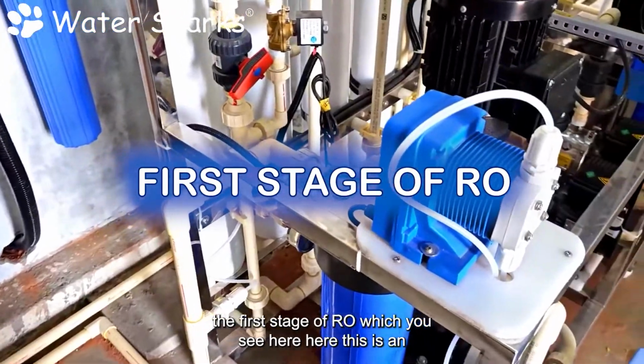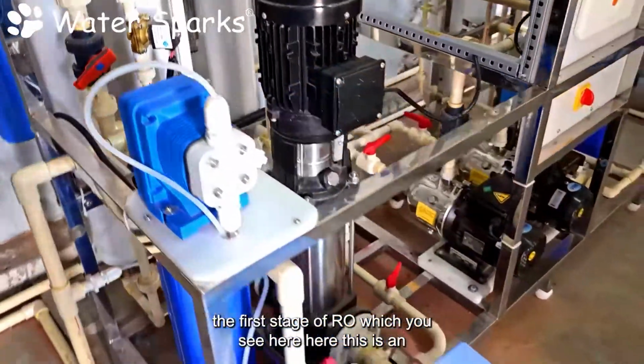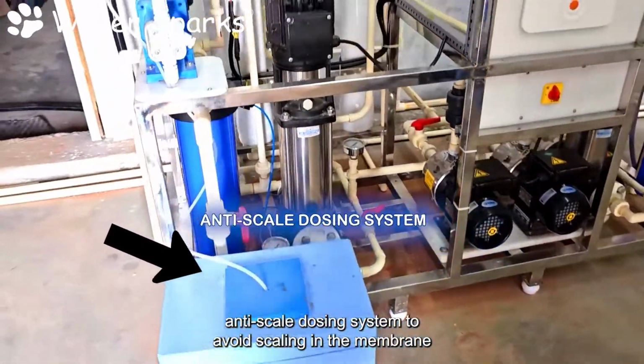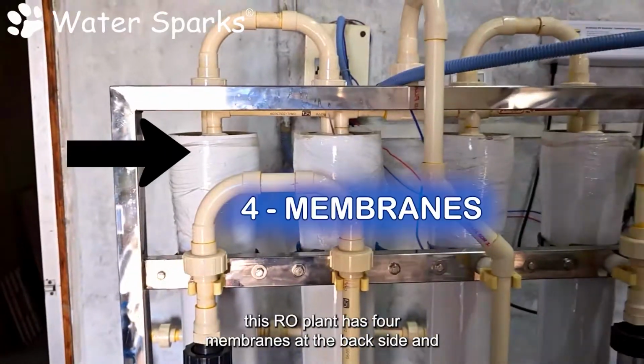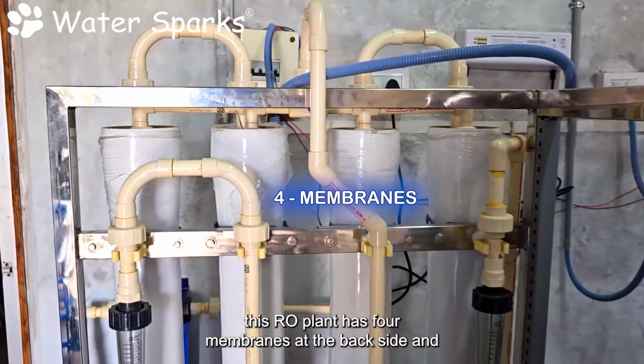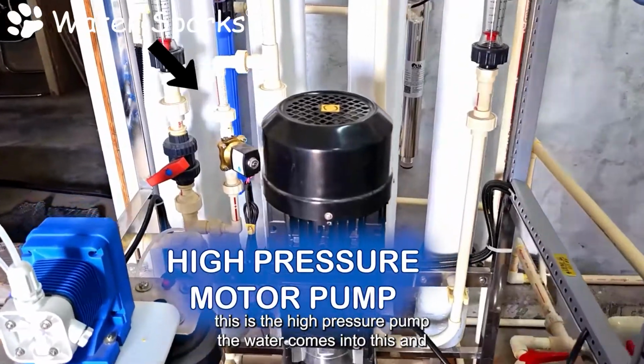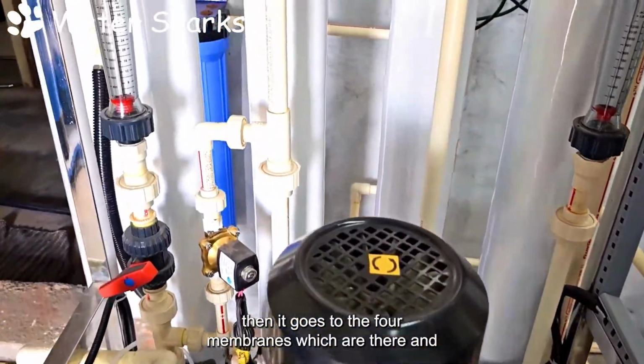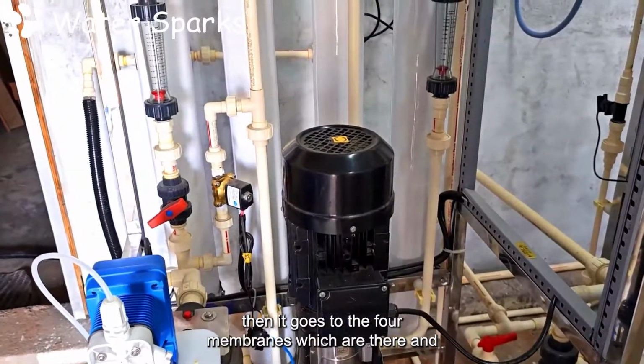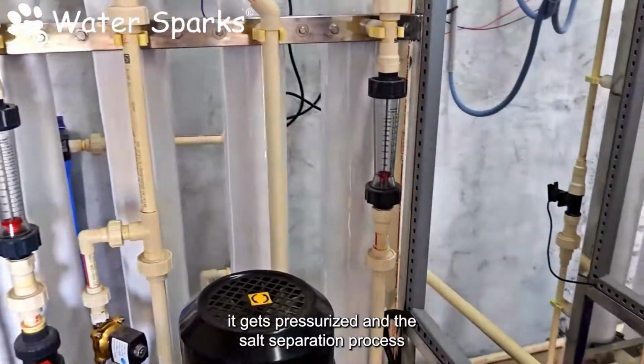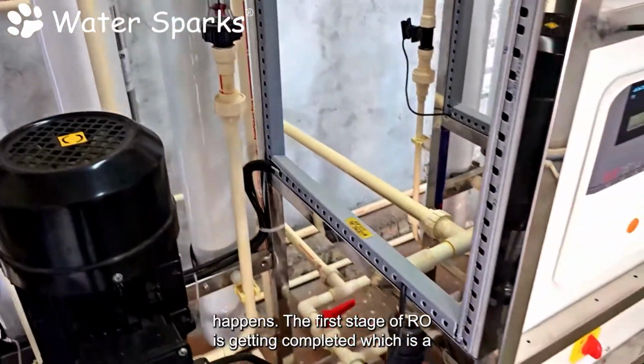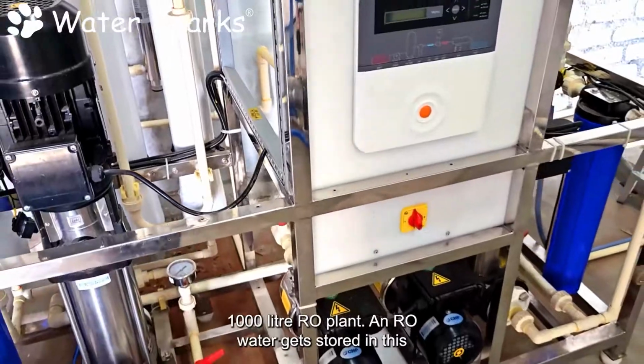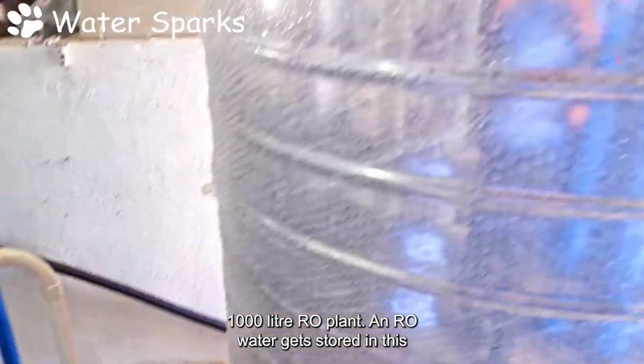This is the first stage of RO, which you see here. This is an anti-scale dosing system to avoid scaling in the membrane. This RO plant has 4 membranes at the backside. And this is the high-pressure pump. The water comes into this pump and then goes to the 4 membranes. It gets pressurized and the salt separation process happens.